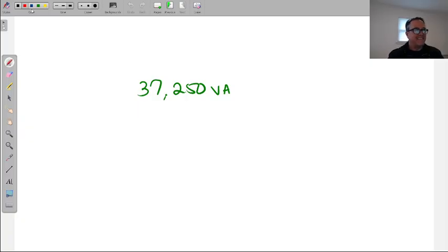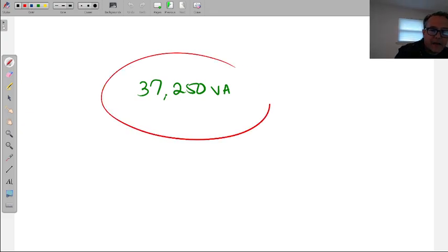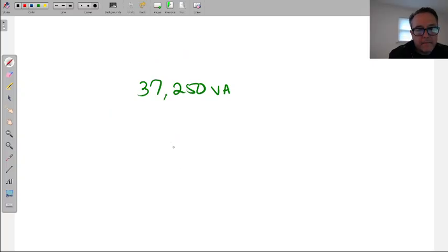All right, how we looking? Has anyone got a different answer from that one? I did. What do you got? So I split it at 30,000, and then you have those two, 525, then you got 3,000, then 1,500, and then 800. Oh, 800 plus 2,800 plus 800, and then 500, right? That right there, and then you gotta multiply that by 0.75. Just two 800s? Correct. Yeah, 800, 800, 2,800, and 500. You add all those together, but you gotta multiply that by 0.75 because it's four or more over 500. Correct. Okay, that's where I messed up.